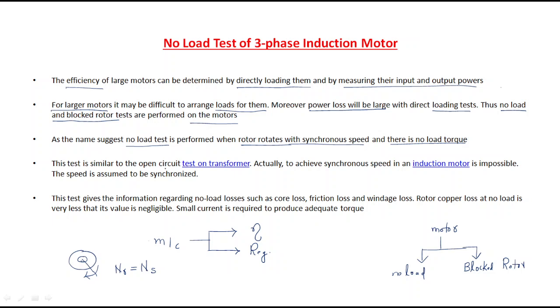This no-load test is similar to the open circuit test on a transformer — this is a very important analogy. When analyzing transformer characteristics, we perform the open circuit test with the same circuit configuration. To achieve synchronous speed in an induction motor is actually impossible; it is assumed to be synchronous. This test gives information regarding no-load losses such as core loss, frictional loss, and windage loss.